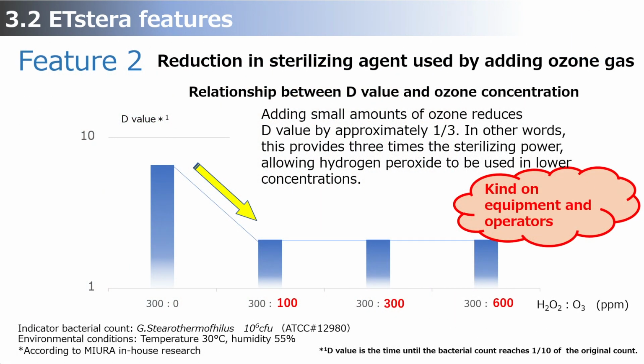The second feature is ETstera's ability to reduce the amount of hydrogen peroxide gas used. Mixing hydrogen peroxide and ozone gas can significantly reduce the amount of hydrogen peroxide used. In addition to reducing the amount of residual hydrogen peroxide, this technique also reduces its toxicity and reduces health risks to operators.